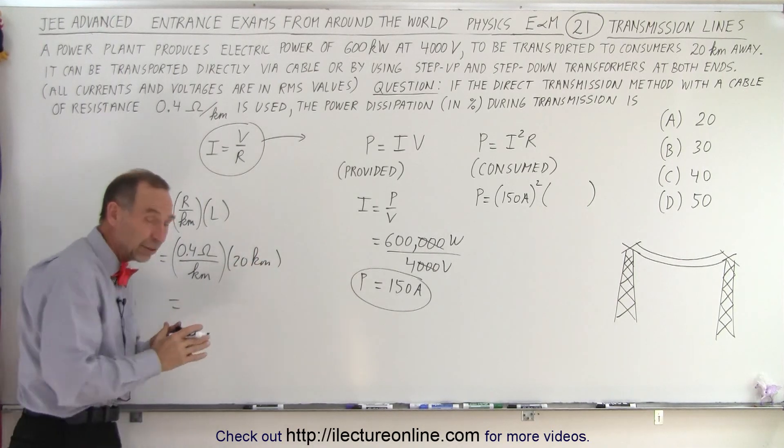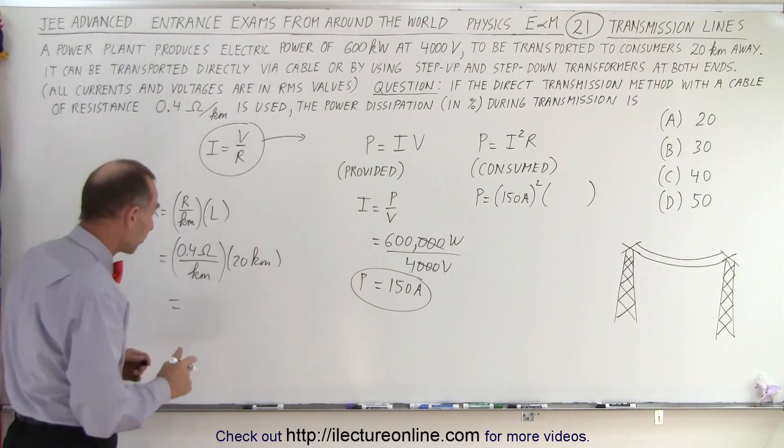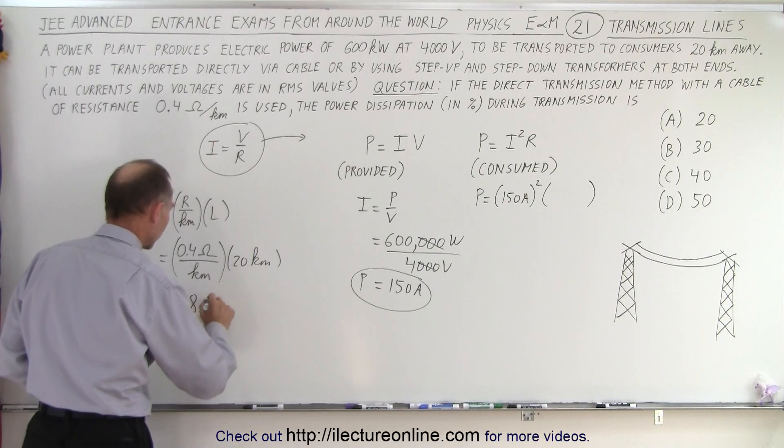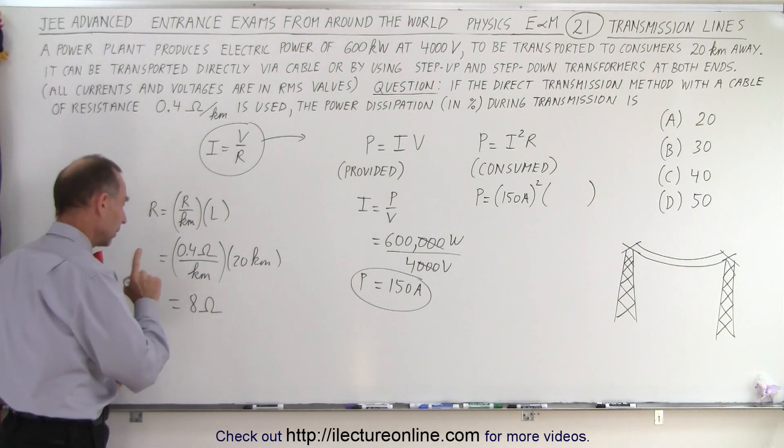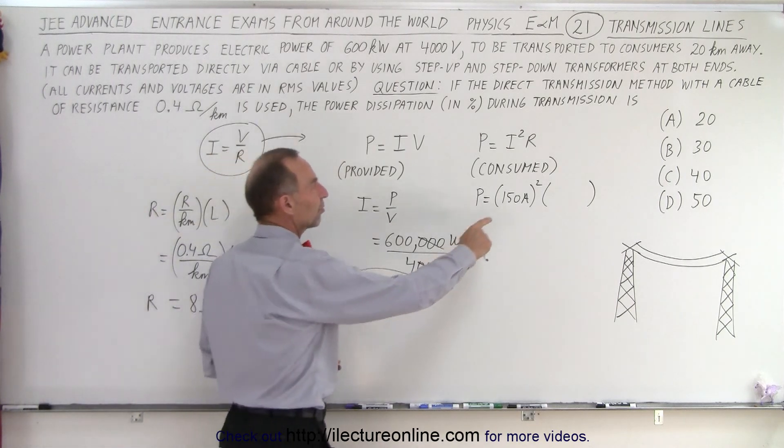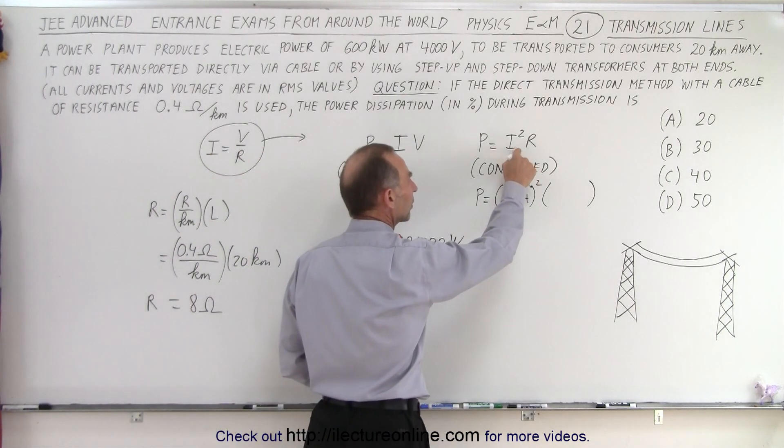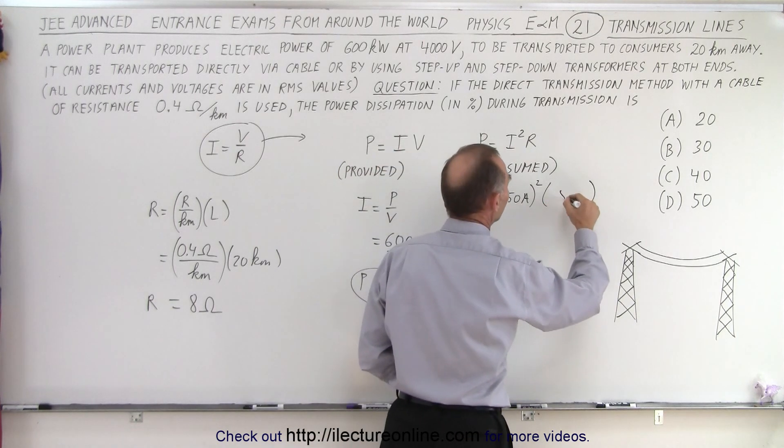So in this case, that is 0.4 ohms for one kilometer, and we're going to multiply times 20 kilometers. That means that over the length of 20 kilometers, the cables have a resistance of 8 ohms. Now you say, well, 8 ohms, that's not very much. Why are you worried? Well the problem is, the current is very high, and you have to square it, so that makes that a very big number, times 8.